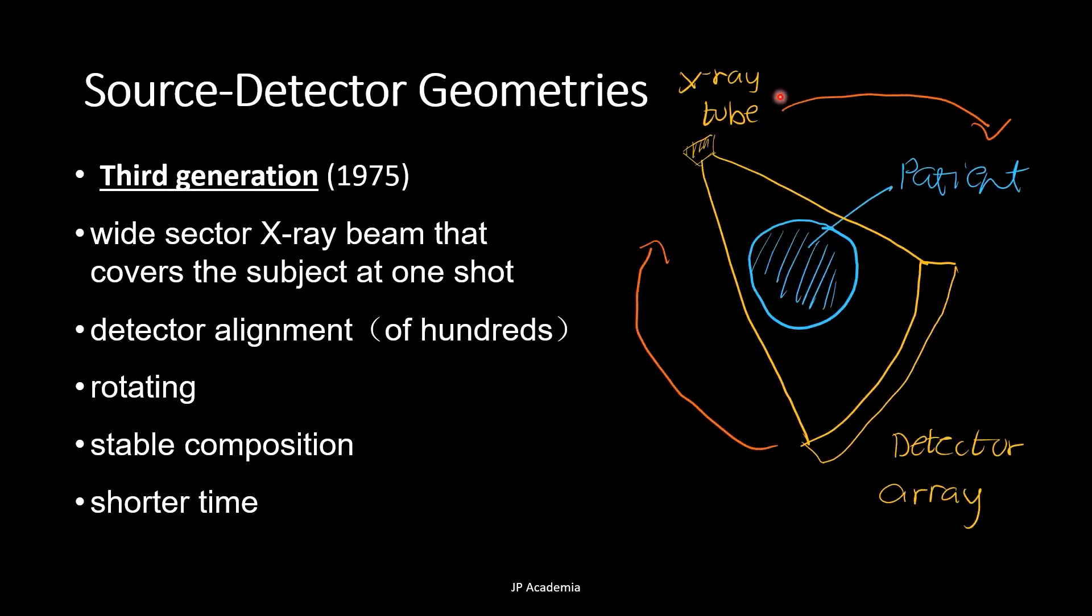Next, we have the third generation, as shown here in the drawing. We have the X-ray tube, we have the detector array, here's the patient, then the motion is mainly rotation. A wide range of fan beam of X-rays encompasses the entire object as shown, and thus it can scan continuously. Fan beam was enlarged to cover the whole field of view of about 50 centimeters. Inclined to produce artificial rings, so that's the disadvantage. And it has a need of highly accurate and stable detectors.